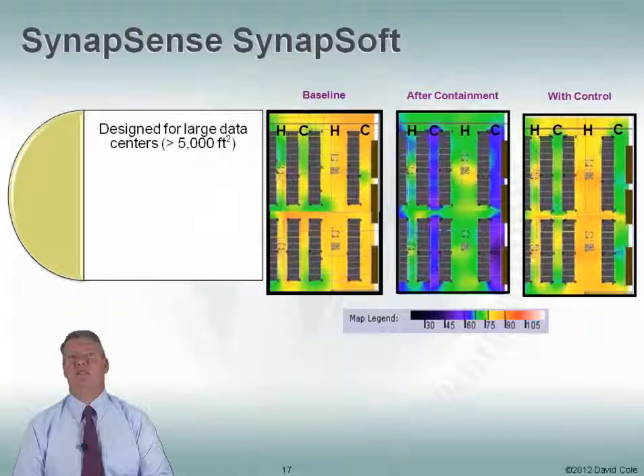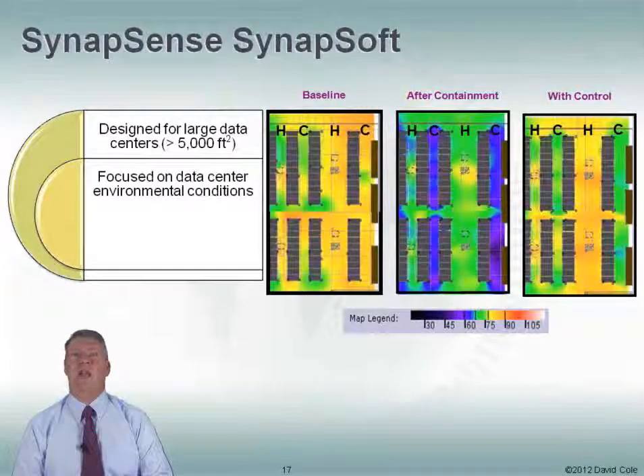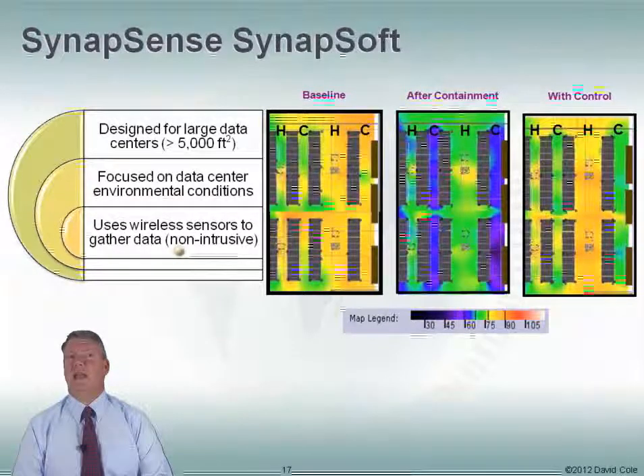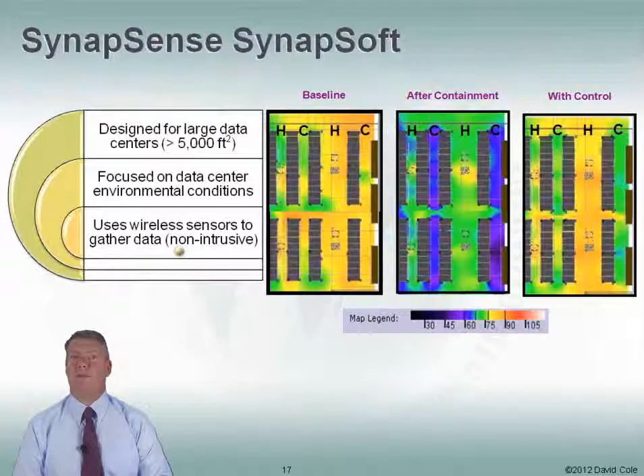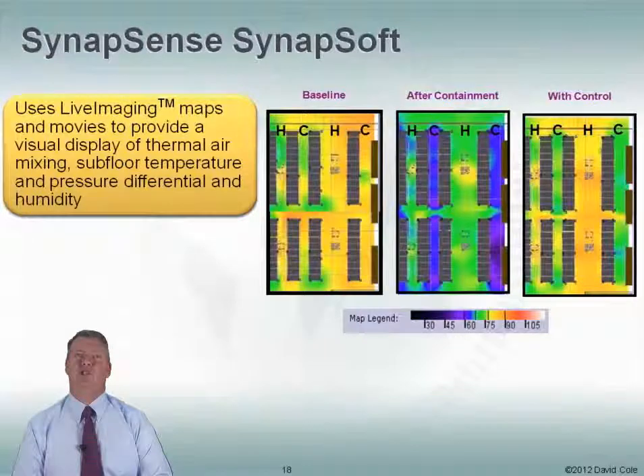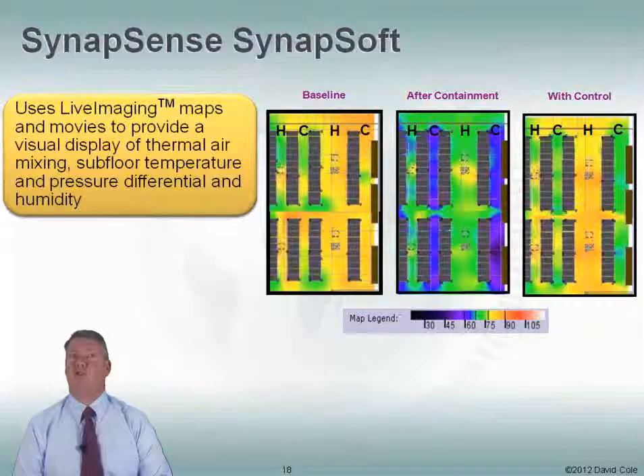Synapsense is not specifically a data center management product — it's really designed to manage environmental conditions, specifically temperature. It's designed for large data centers, maybe greater than 5,000 square feet, and is really focused on data center environmental conditions. They use a lot of wireless sensors to gather data, so they're non-intrusive — you can pop these sensors wherever you want. It uses something called live imaging, which can map your temperature changes to movies. You can say, show me what my temperature looked like over the course of a day, month, or year, and see how temperatures change. It can also look at pressure differential, humidity, and whatever the sensors support.